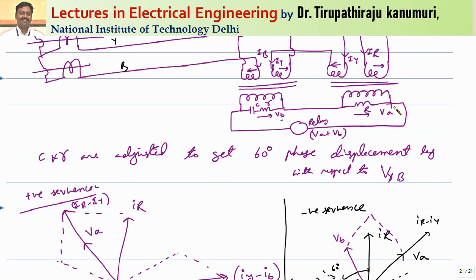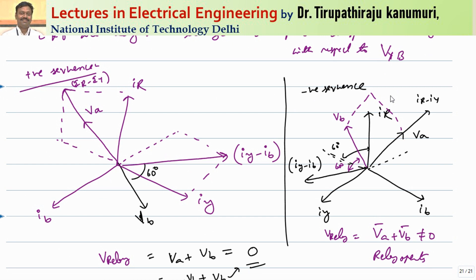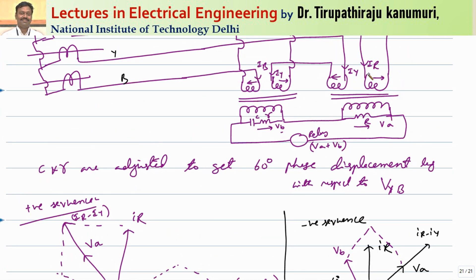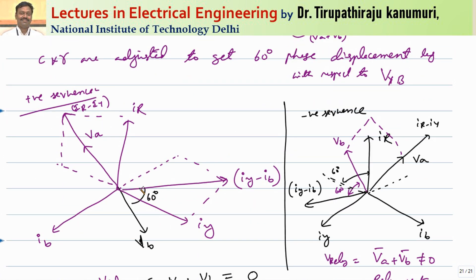VA is designed to be in phase with the corresponding voltage. For positive sequence currents IR, Iy, IB: the first transformer carries IR − Iy, and VA is in phase with IR − Iy. The second transformer carries Iy − IB, and by tuning, VB lags those currents by 60 degrees. This results in VA and VB being in opposite directions, so their vector sum equals zero — the relay does not operate for positive sequence currents.